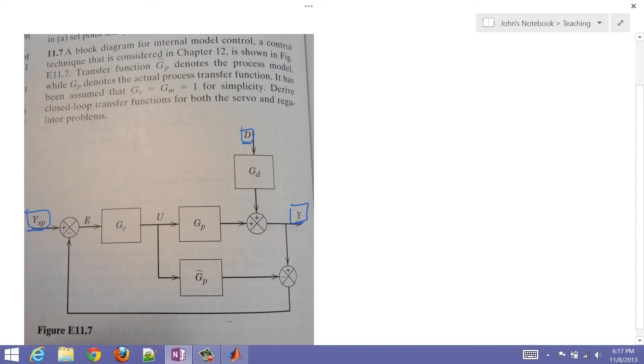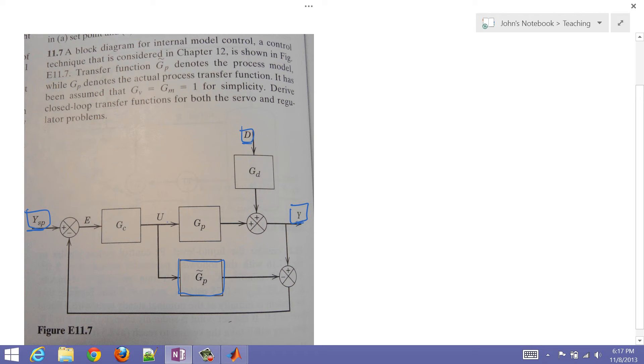Let me explain this block diagram first. This is a controller, and it operates off of an error between my YSP and something that's in a feedback loop. This is my manipulated variable — a thing that I can actually change in my process, the actuator. This is my process. This is a disturbance transfer function. And this right here — if you didn't have this, it would be a standard feedback control loop. But this is actually a process model of my process, and what I'm doing is running these two in parallel — my actual process and then my model — and then taking a difference between those two, and that's actually what the controller operates on.